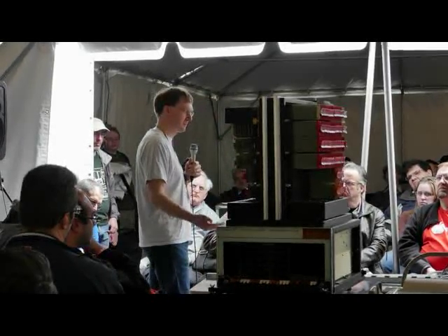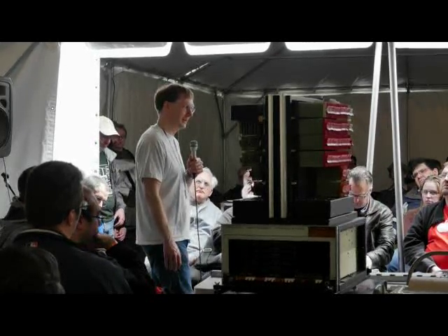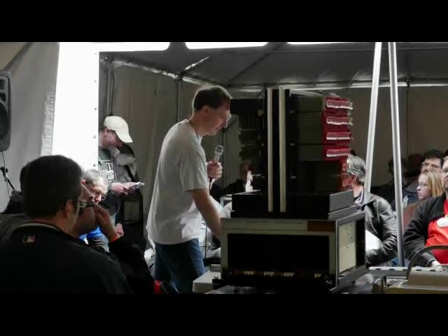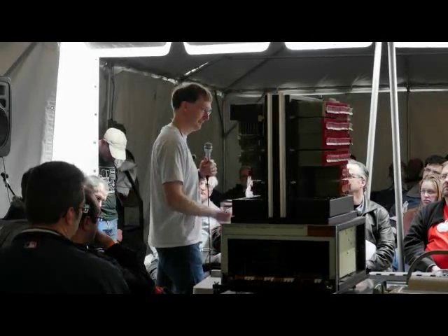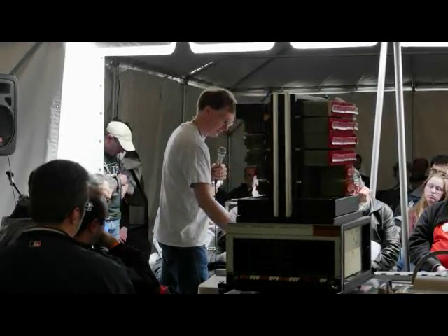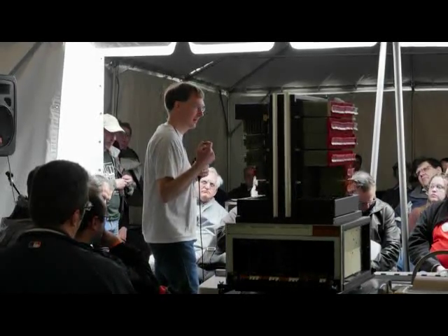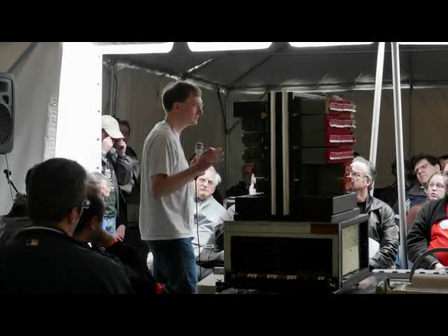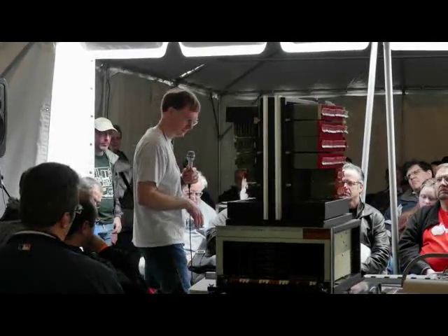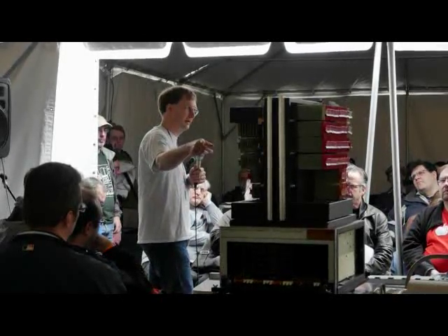And I did notice, while I was going through here, that there's evidence that there have already been a number of repairs made to this machine, based on the flux residue and damage to pads from when they had done the repair previously. So it was not entirely reliable even when it was new. And like I said, there's a couple other issues. The diodes are glass encapsulated, and there's a bunch of them with little chips out of the glass. I don't know if that's due to the corrosion stressing the glass, so it's unclear whether that's going to drive the failure of components. Like I said, they're looking into new plastic covers. Some of the paint on the front panel is deteriorated.